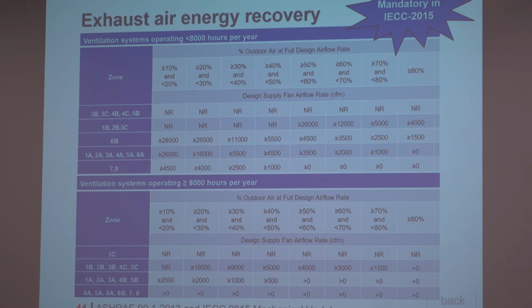So exhaust air energy recovery is a little different between 90.1 and IECC. The table's the same. IECC is mandatory, 90.1 is prescriptive. So one of them you can trade, the other one you cannot trade. And the way that this table works is a little complicated. Let's look at the upper table. Depending on what climate zone you're in, so let's do 5 and 4A, because that's where we are, and depending on the total CFM of the unit, if we have a large unit, 26,000 CFM, and we're at 10% to 20% outdoor air, we need to have an energy recovery ventilation system.